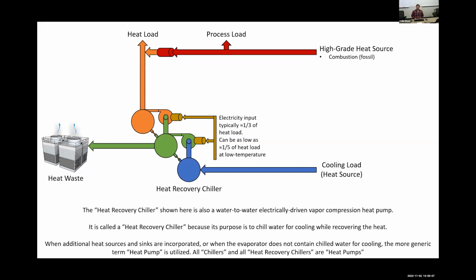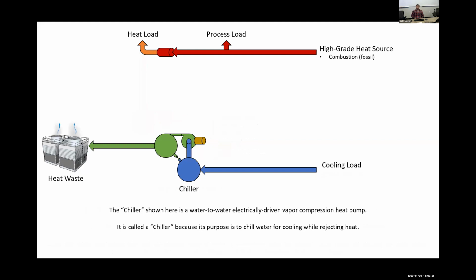So UC Davis has a steam distribution system, which is fairly common across universities in the United States and across the world. That is distributed to the buildings, utilized for processes, and then converted to a lower temperature heating hot water. I'd actually jumped a slide there. And then the cooling system is typically a chilled water distribution system that comes back to a chiller.